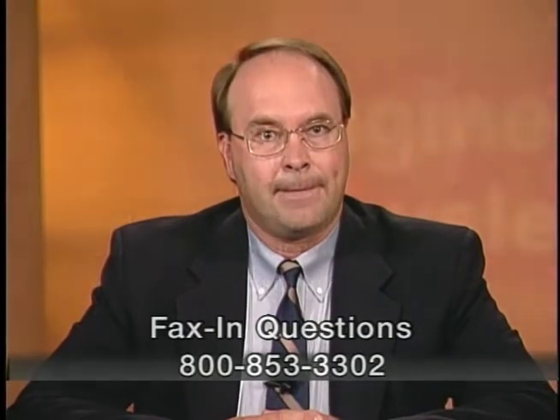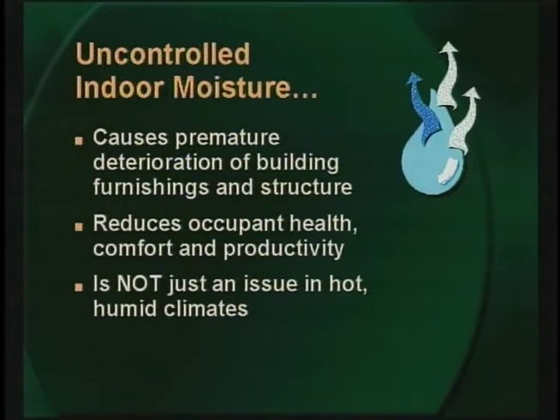We're hearing a lot about controlling moisture in buildings these days, and for very good reason. High indoor moisture can cause a variety of problems for the building structure, its furnishings, and most importantly, the occupants. Moisture, either in the form of liquid water or sustained relative humidity levels over 70 percent, can support the growth of microorganisms such as mold and mildew, and increase the activity level of dust mites. Areas of the building like walls, ceilings, and furnishings such as wall coverings and carpet all provide ideal amplification sites for fungi. The resulting growth produces foul odors and releases allergens and toxins which can aggravate pre-existing respiratory problems such as asthma and actually cause other types of lung disease.